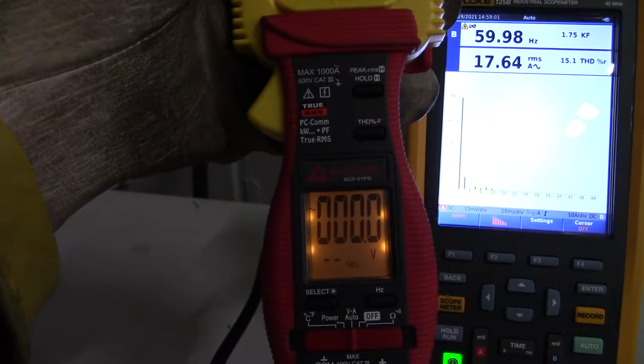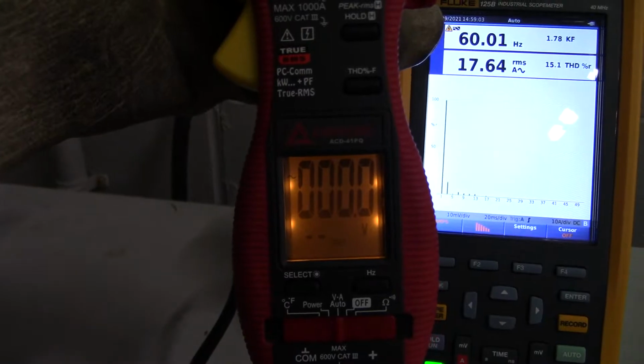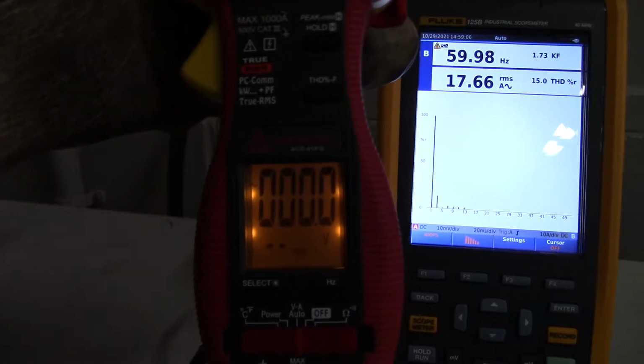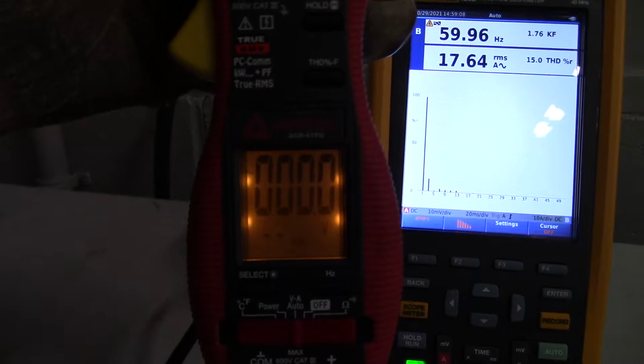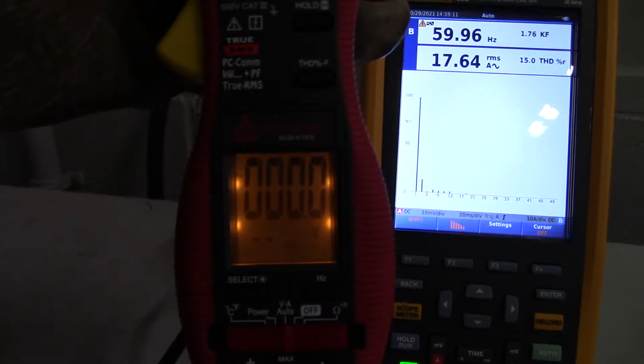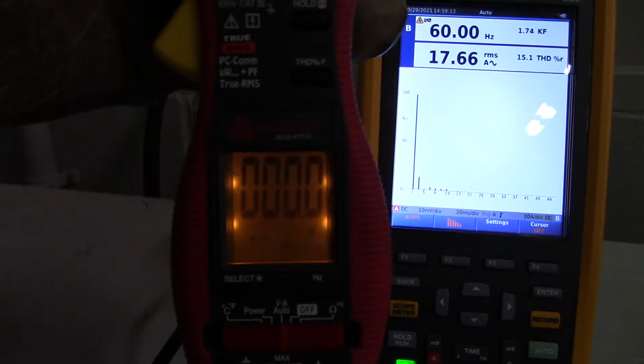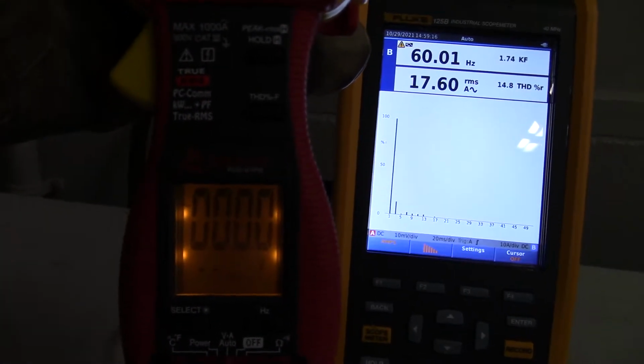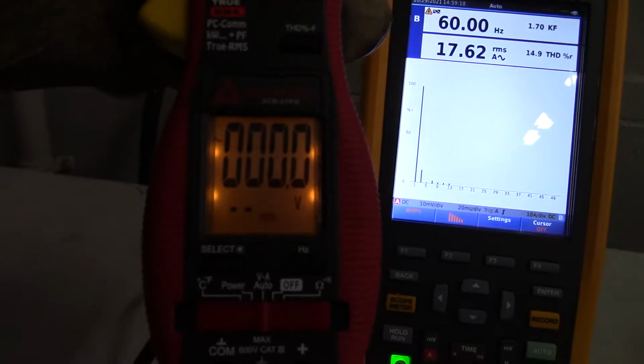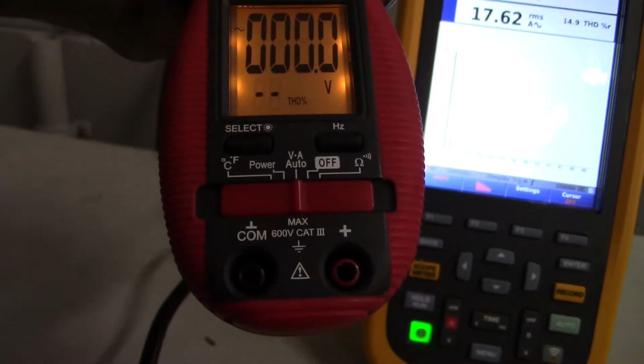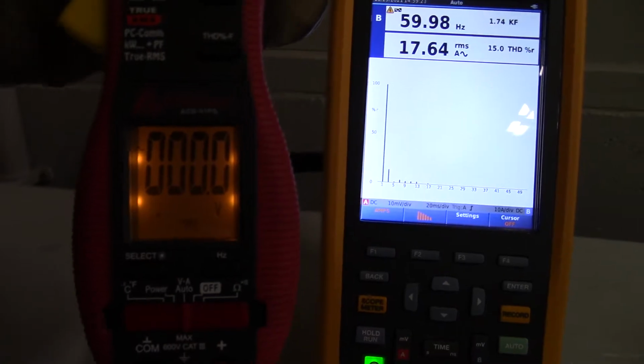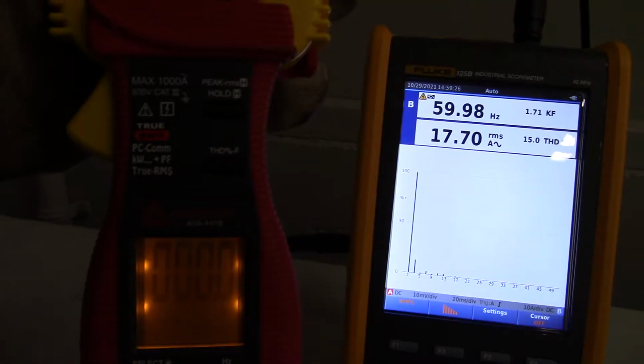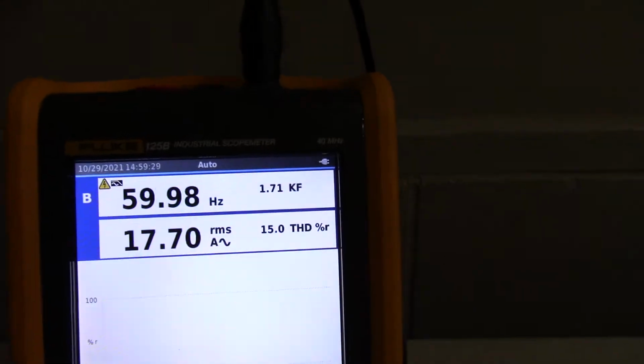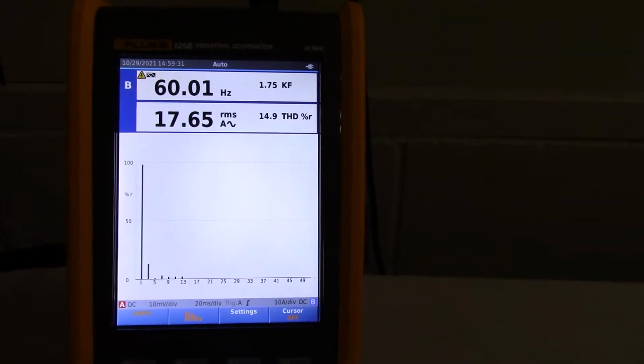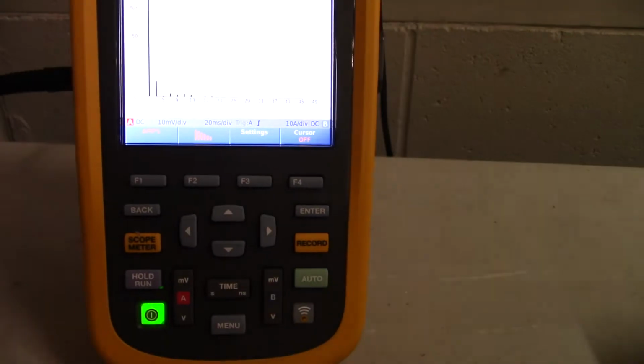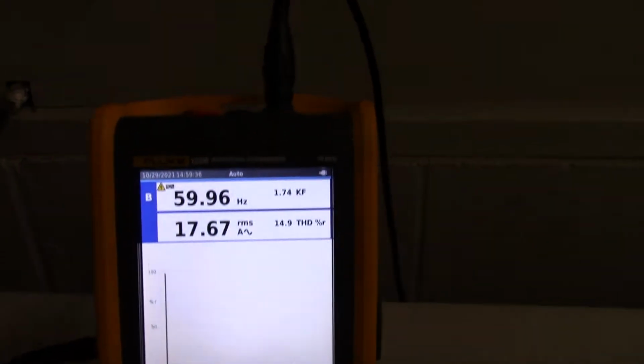Okay, we are going to measure total harmonic distortion using this Amprobe ACD-41PQ meter that measures total harmonic distortion in both the current and voltage waveform. It also performs other power quality measurements, but we're studying harmonics right now, so we're going to use it for that. I'm going to compare the values that I read with this guy right here, which is a 125B industrial scope meter with a harmonics measurement function.